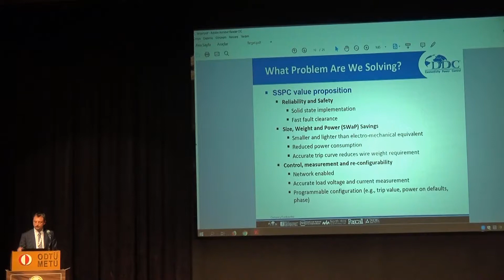Hidden cost benefits, as I explained: improvement over mechanical circuit breakers and relays, reduced inventory because you need basically one card to replace 16 standard circuit breakers, standard configurable card modules, as I said and explained before. You can program the channels according to the needs in the system.